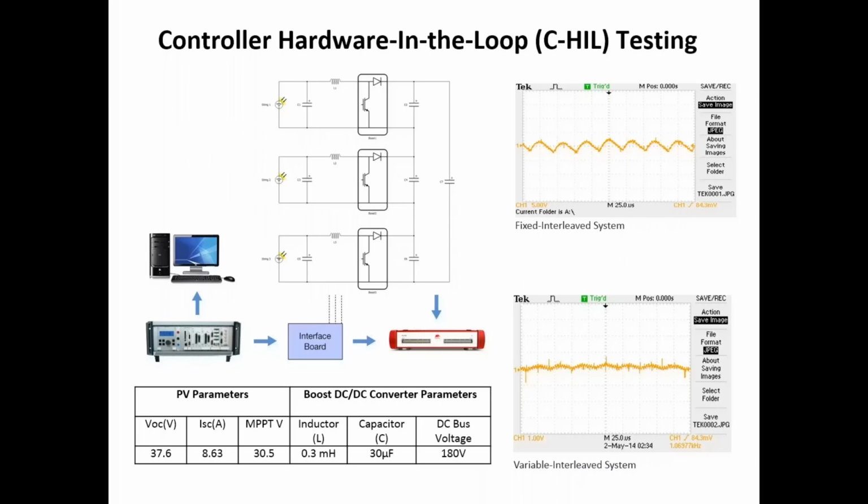And at that time, we still did not have real-time simulators, and so we actually built up simulators in an analog-digital fashion. And controller hardware in the loop was done because that is how we developed our controls. That is how we showed the customer or the utility what these devices would do in their system. And we went through all the fault cases.